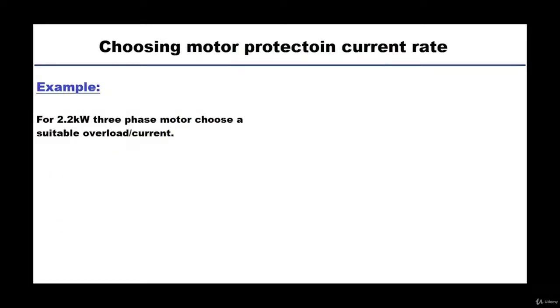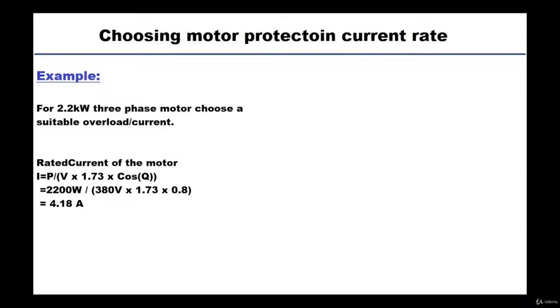Now let's take an example and try to choose a protection for this motor. The rating is 2.2 kilowatts and it's three-phase, and we'll assume that it's running on 380 volts AC. First, we need to calculate the current consumption of this motor, and here we're going to assume that the power factor for this motor is 0.8. And from the formula we learned before, we get 4.18 amps.